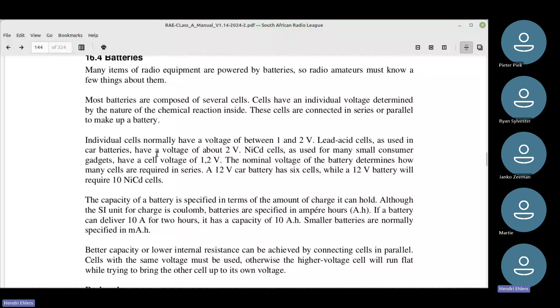But the charging of NiCads and the charging of lead acid is completely different. A lead acid battery uses constant voltage, constant current, but a NiCad battery charges to a point where the voltage goes up and then it drops, and you need an intelligent charger to see the drop in the voltage and then stop charging. Because if you continue to charge the NiCad battery, the voltage will reduce to the point where it looks like a flat battery, and it will heat up and eventually destroy itself. So you can't use a constant current, constant voltage power supply to charge NiCad batteries. You need what they call a peak detection charger. The capacity of a battery in terms, yeah, nickel metal hydrides compare?